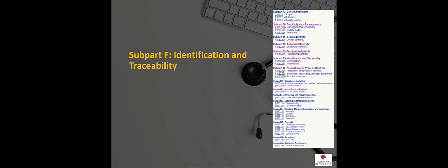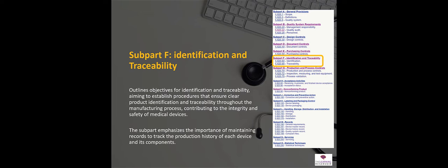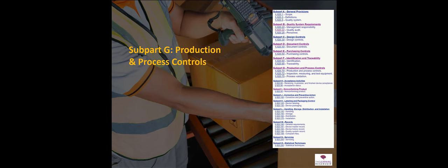Sub-part F covers identification and traceability. This is critical. We need to be able to track medical devices when they go out into the field, we need to be able to identify them, and we need to have full traceability if we have to do a product recall — we want to be able to do that effectively and efficiently, and that's all covered under sub-part F.